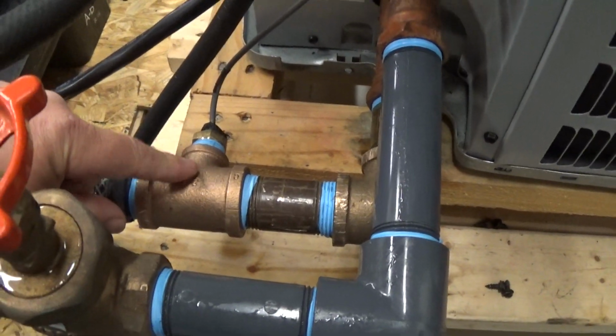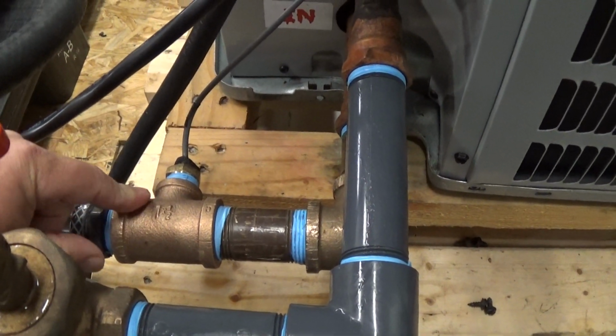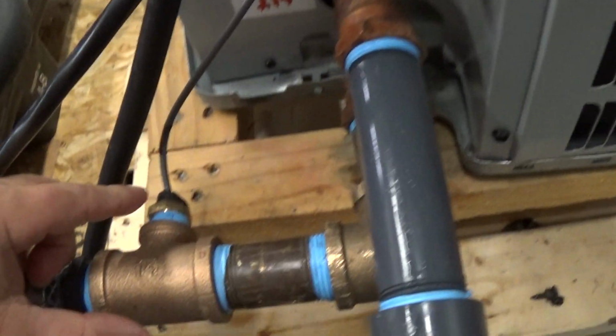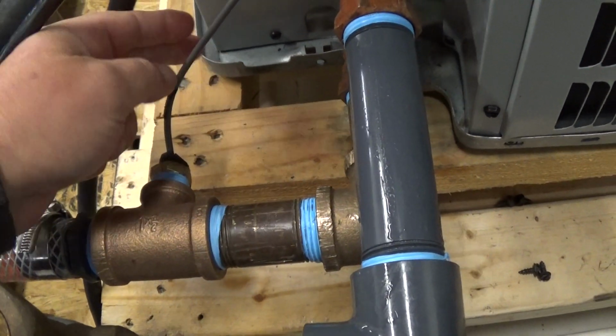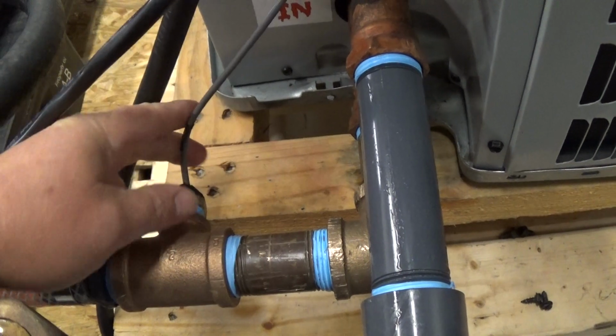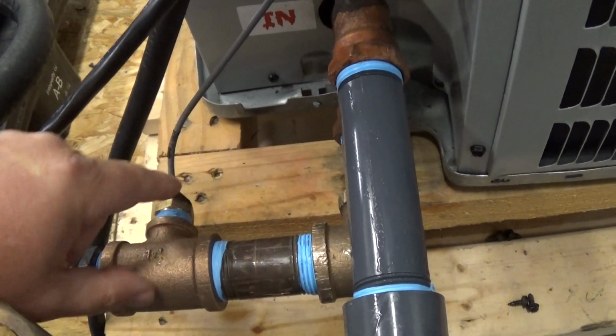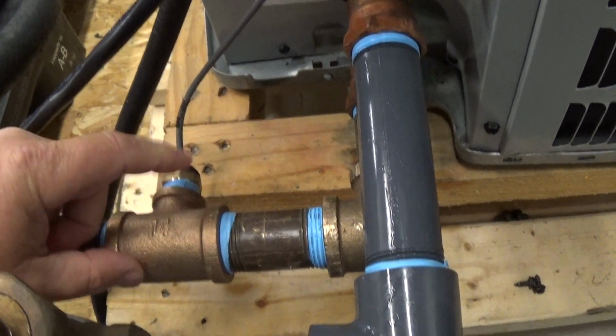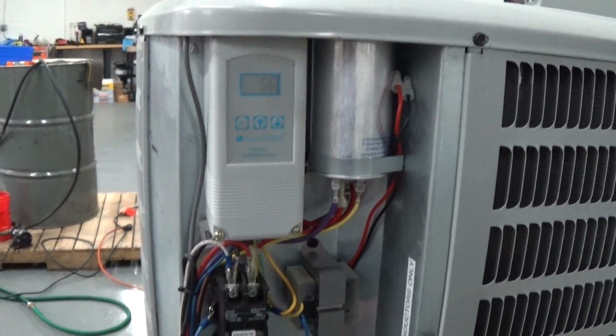Included though is this T. This T, the inlet to the chiller, has a well on it, and that is where we're actually sensing the temperature. Okay, so this inlet coming back to the chiller will have this T, and this is where your temperature probe is. The control system is sensing that temperature here.